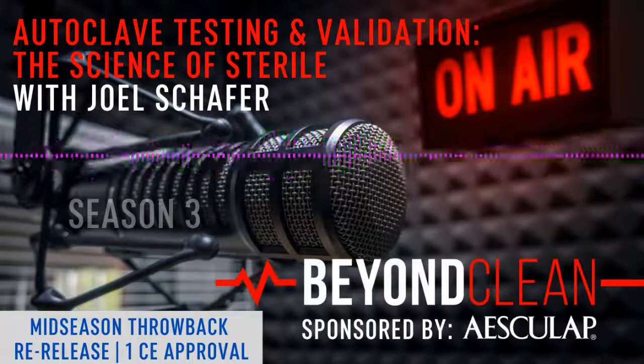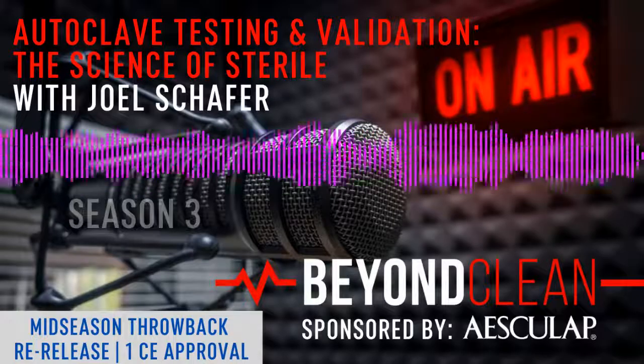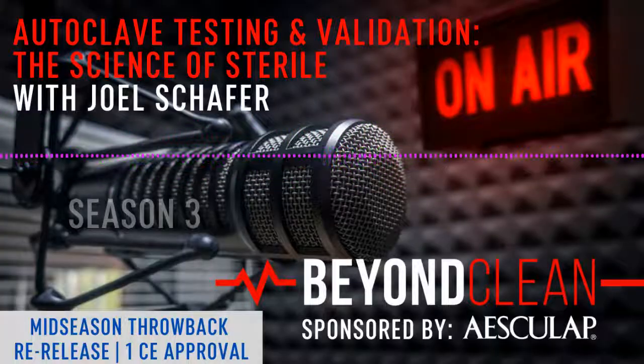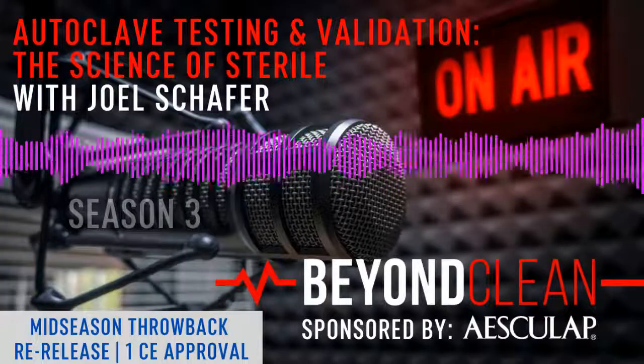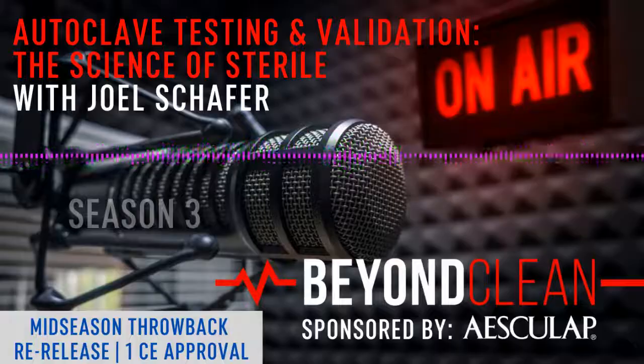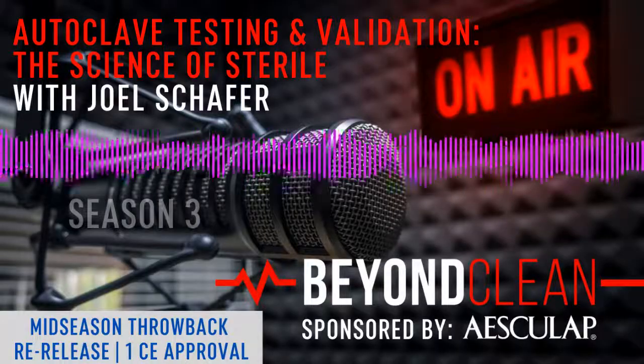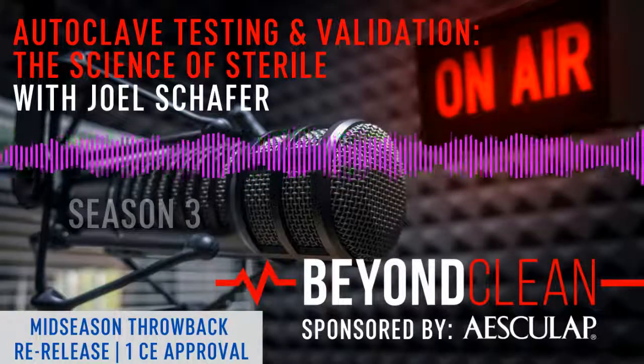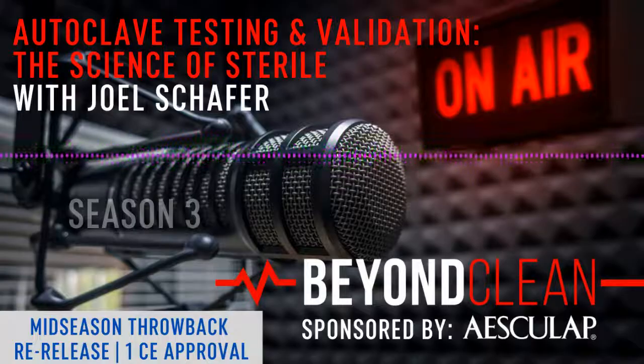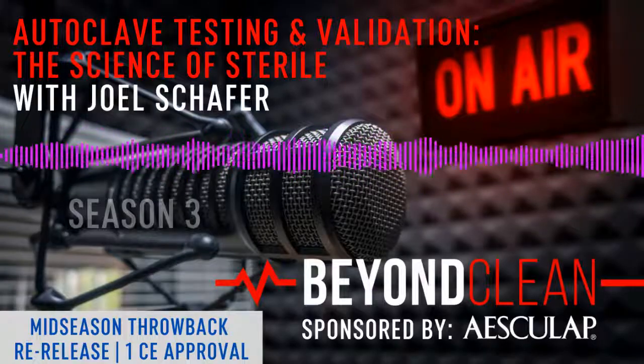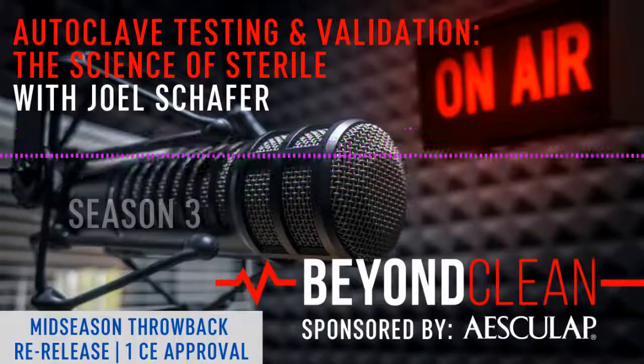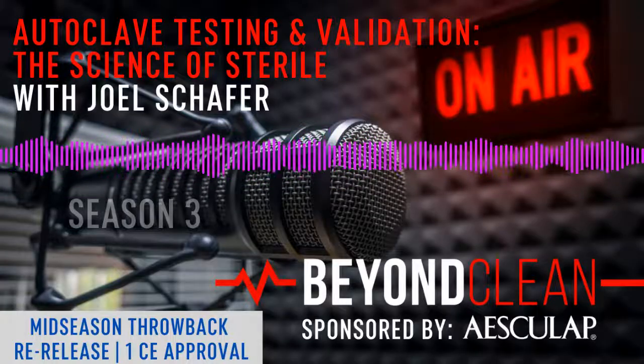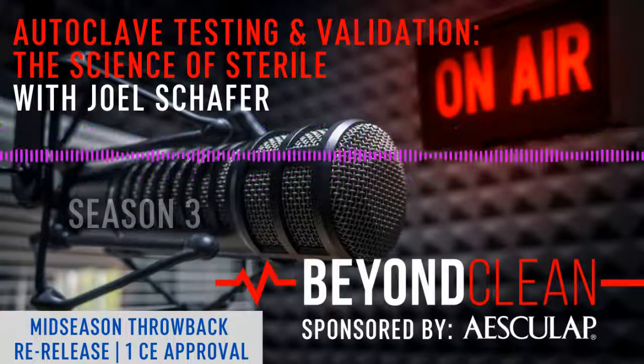Why don't we just start at the beginning, talk about autoclave testing, maybe give a background on that, and also validation, and why is so little known about it in the United States? Well, testing is really more akin to the daily tests that we all do in the sterile processing departments, the biologicals and the Bowie-Dicks. That's not really a validation per se. That's more of a verification.